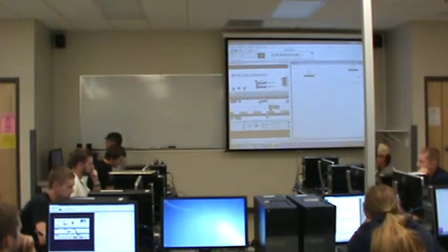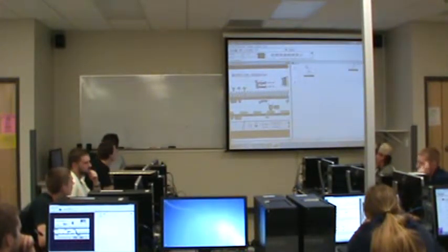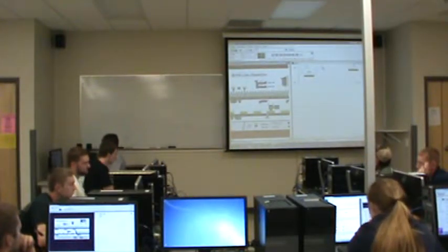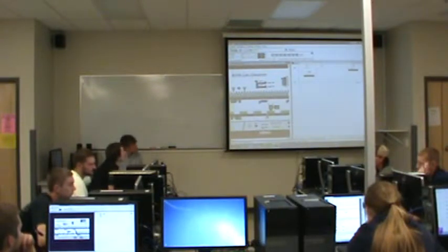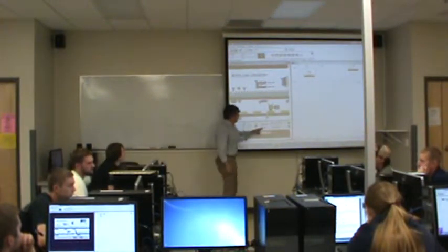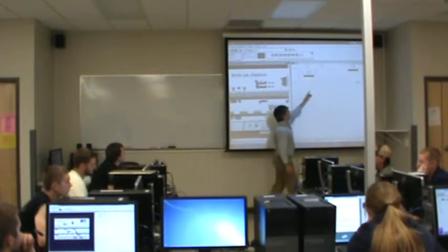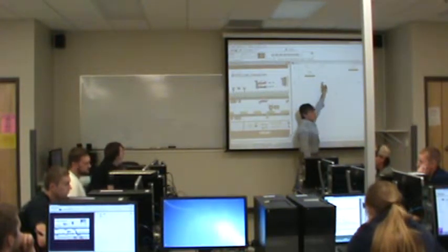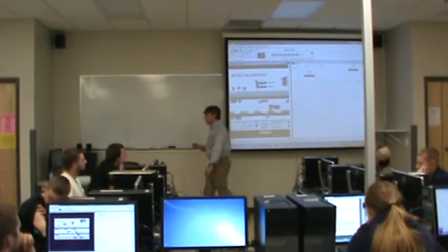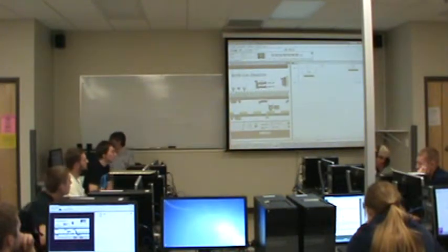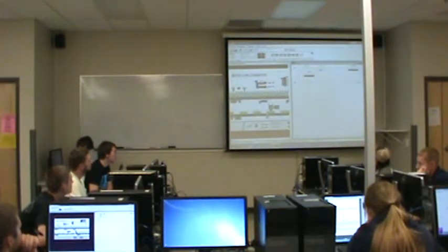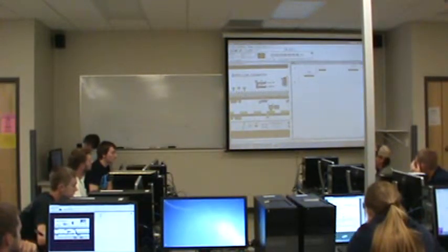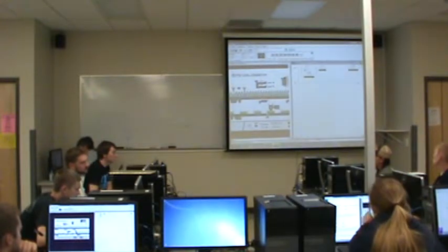Okay, so let's copy the address over here so that once it comes on, it seals in. We'll drag the address of the start button in here and the stop button in over here. As usual, this is a normally closed stop button. So you can see when I hover above it, it says NC, which means this normally passes power. That means that the instruction that references that button is going to normally pass power as well. So it will normally be true unless the button is pressed. And that's the way I want it to be. So let's right-click, edit symbol, stop button. Right-click, edit symbol, start button.